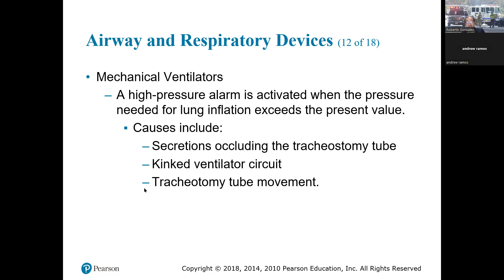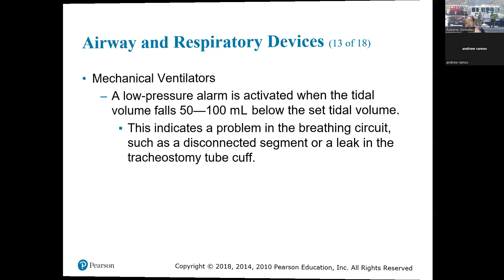A low pressure alarm is activated when the tidal volume falls 50 to 100 mLs below the set volume. This indicates a problem with the breathing circuit, such as a disconnected segment or a leak in the tracheostomy tube cuff, which, remember, I told you that all these have a little cuff that you inflate. Most of them, not all of them.